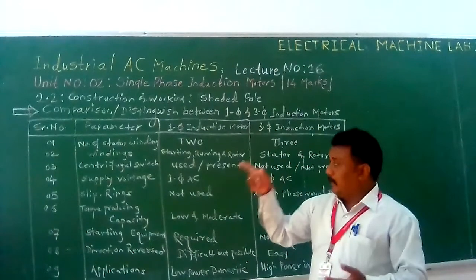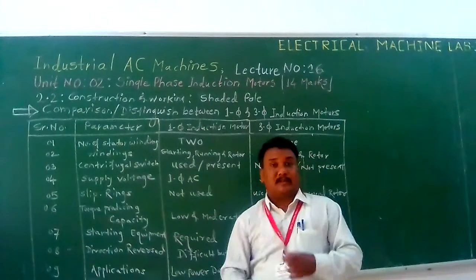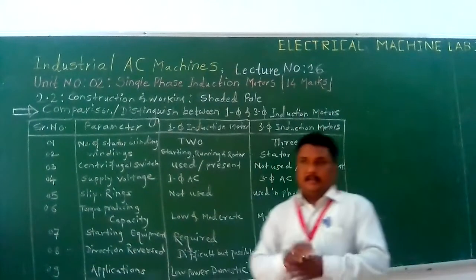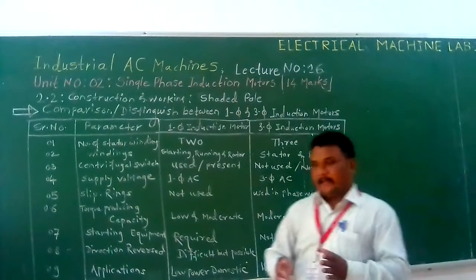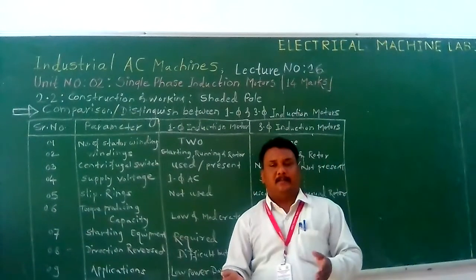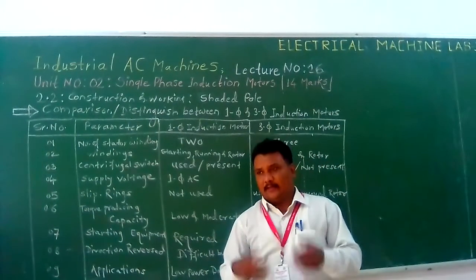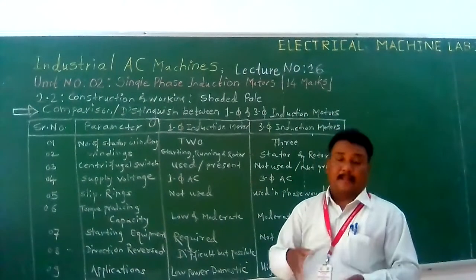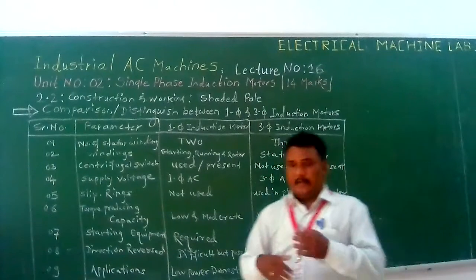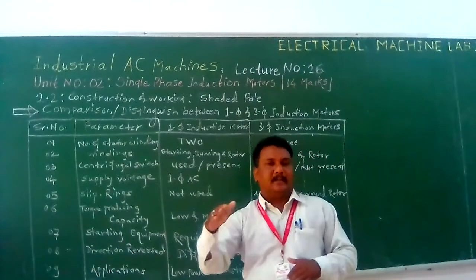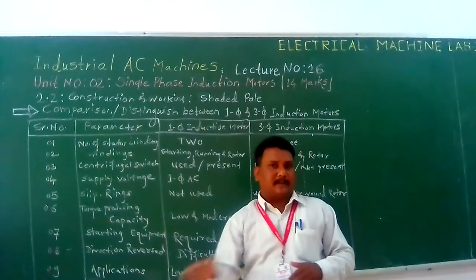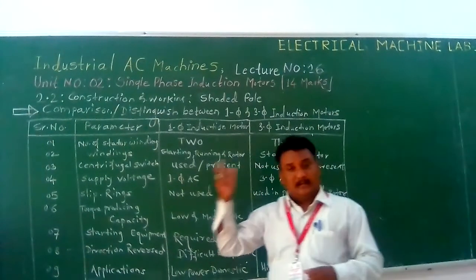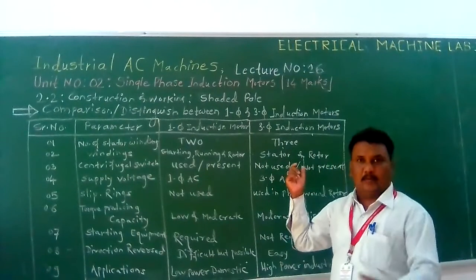Without it, the motor cannot transfer from starting to running mode, because the starting and running windings have a 90 degree phase split, and without the centrifugal switch the running winding cannot be accessed. Whenever the running winding appears in the circuit, the starting winding is automatically cut from the circuit. In a three phase induction motor it is not required, hence not used or not present.